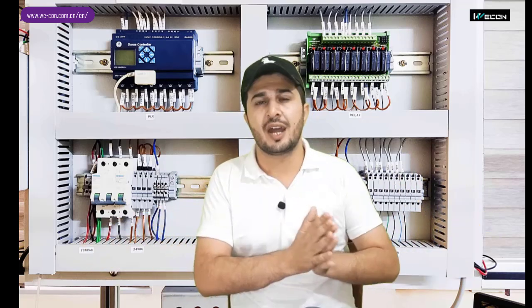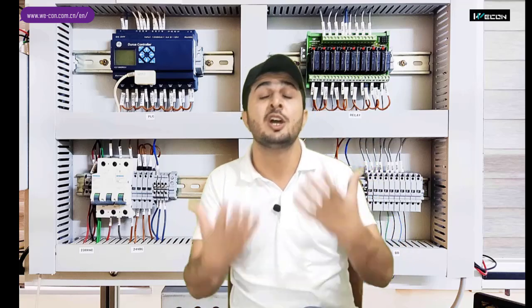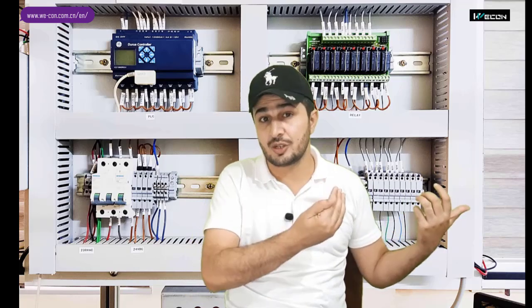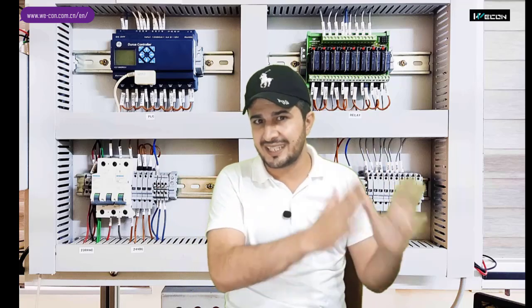Another difference between PLC and SCADA: in SCADA there are different programming languages. Like VB, you would mostly be writing a script in VB in a SCADA system, whereas when we talk about PLC, the languages are like ladder, FBD, STL. PLCs don't store historical data, whereas SCADA systems normally store your historical values. So if you want to see the pressure value or different process parameters in history, maybe 1 year back, 2 years back, 10 years back, you would be relying on the SCADA. PLC would definitely not help you in that case.